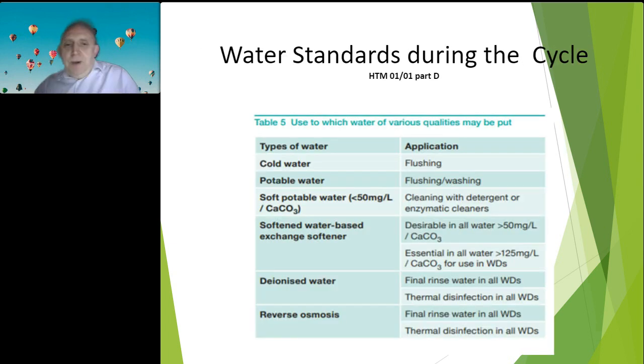So when we go back to our HTM 0101 Part D - if we look at the flush application, cold potable supply is appropriate. If we look at our cleaning using detergents or enzymatic cleaners, we need to have soft potable water. Softened water must not interact with any process chemicals we are actually using. If we think of our final rinse, obviously that's the final stage of the wash disinfect process, we need to have water of a high level of purity, and typically we use systems called reverse osmosis for that stage of the process. It doesn't have to be RO, however that does generally tend to be the more common method we use across the UK.